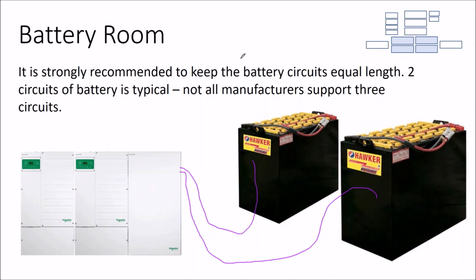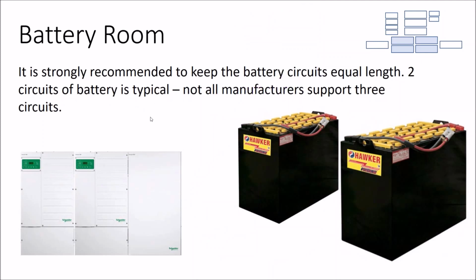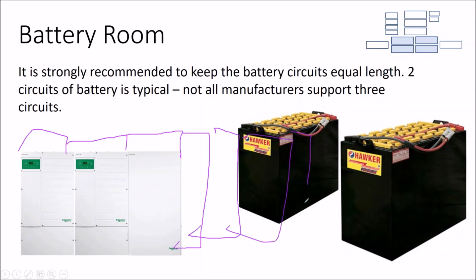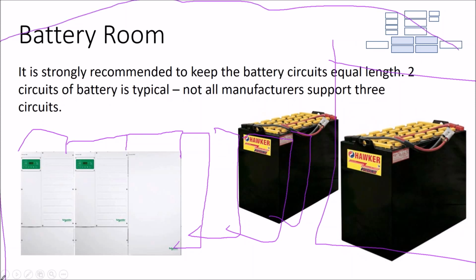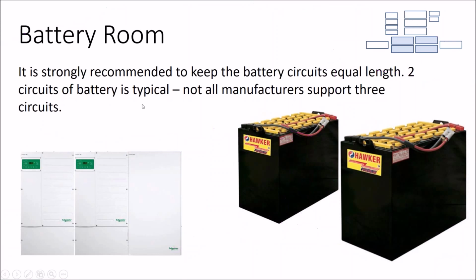So often you'll see customers either stack them on a shelf and put the inverter service panel right next to it. You get out of some disconnect requirements if the run between these two systems is 5 feet or less. And what that means in a battery room is you might have 2 inverters here, and then your service panel, and then 4 charge controllers, and then a giant battery bank that might be 12 feet long. So the total wall of your room might get to be 20 feet long, or you could turn a corner or something like that.